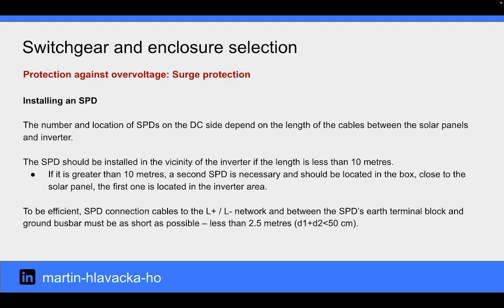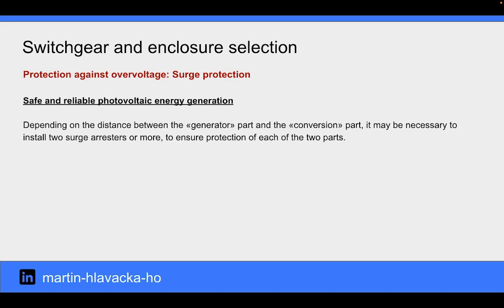To be efficient, SPD connection cables to the line positive - line negative network and between the SPD's earth terminal block and ground bus bar must be as short as possible. Depending on the distance between the generator part and the conversion part, it may be necessary to install two surge arresters or more to ensure protection of each of the two parts.